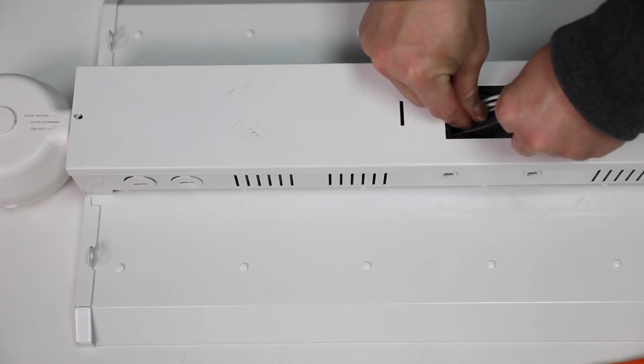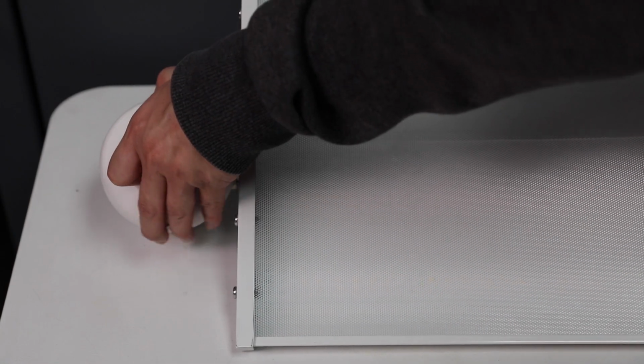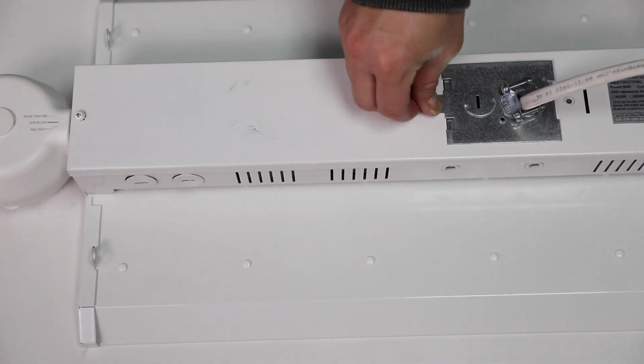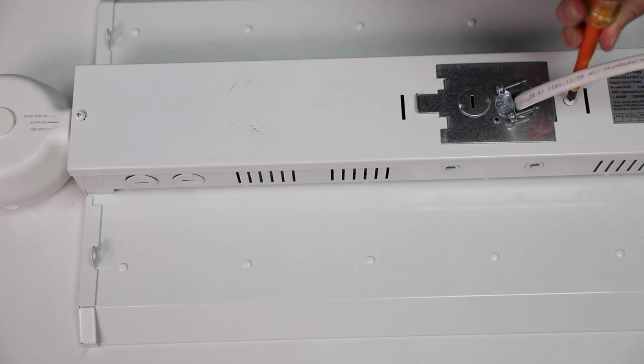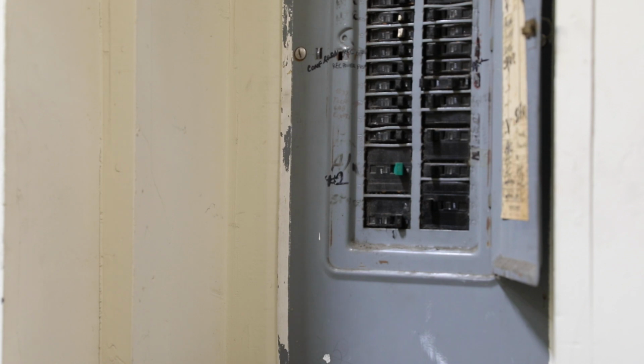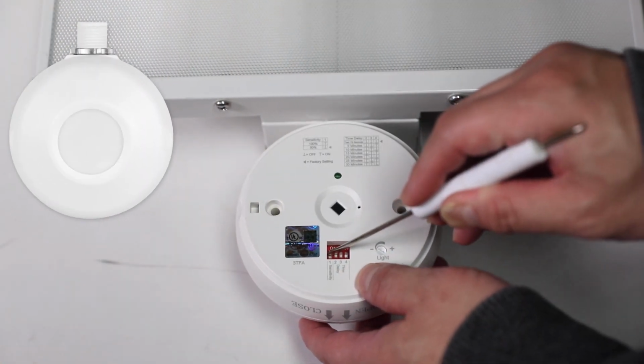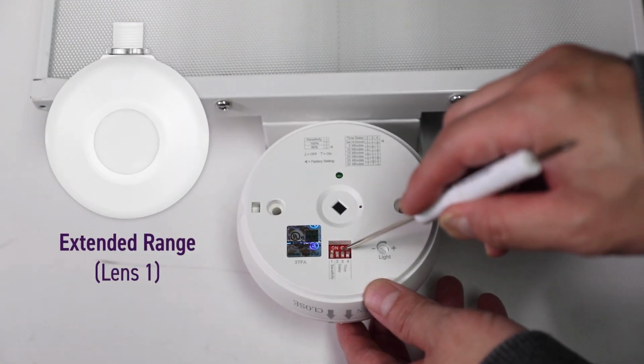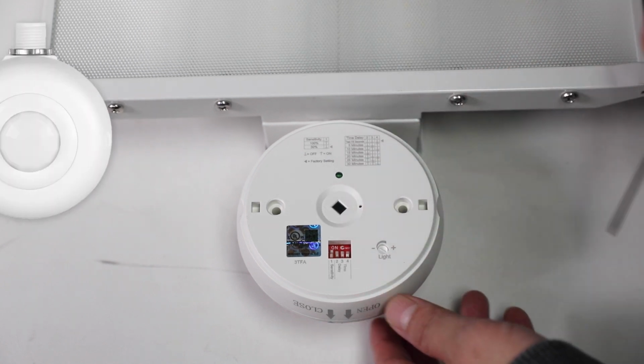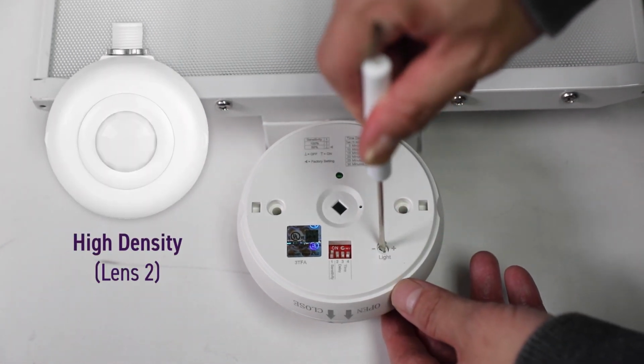Tuck the wires on the sensor into the housing and twist the sensor to lock it on. Tuck the wires in on the light fixture and install the access covers and light bulbs. Turn the power on at the circuit breaker. Adjust the settings and install the extended range lens if the height of the sensor is above 10 feet. Use the high-density lens if the height of the sensor is at 10 feet or below.